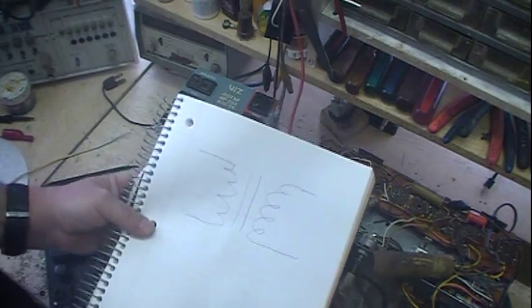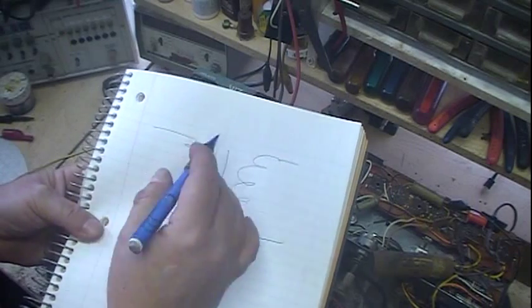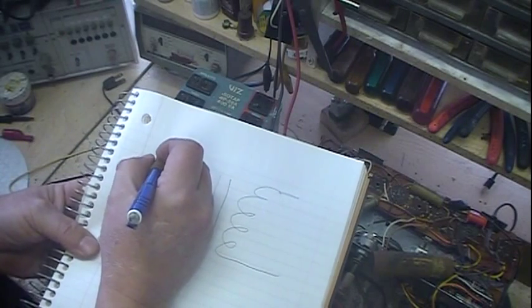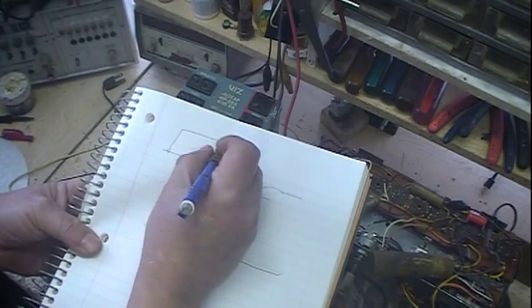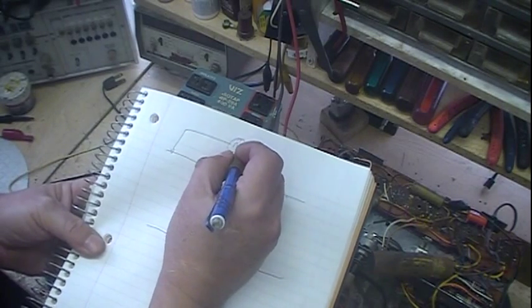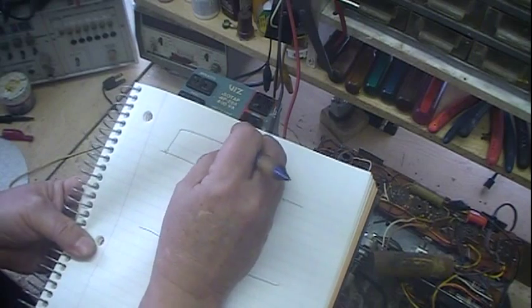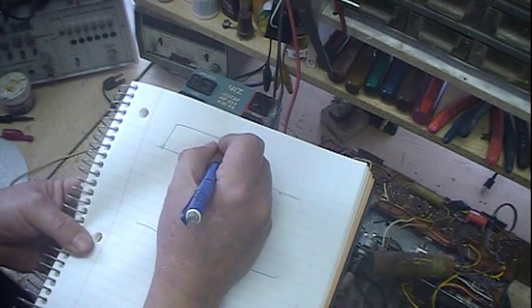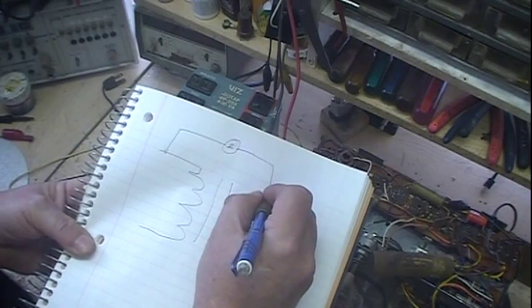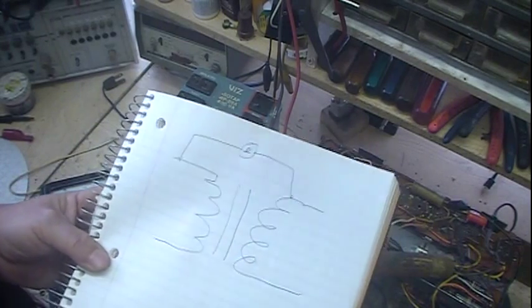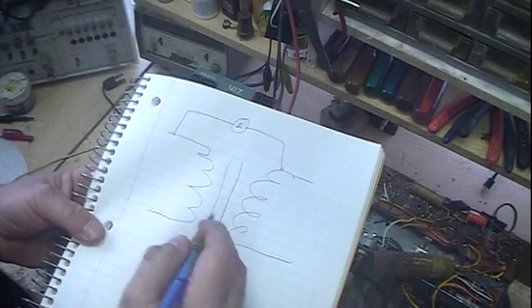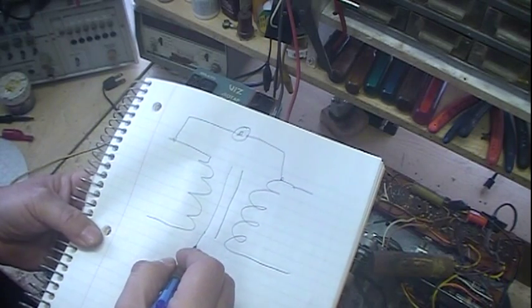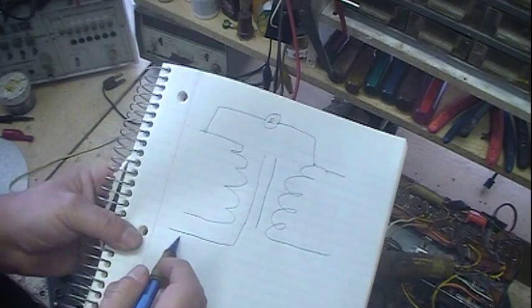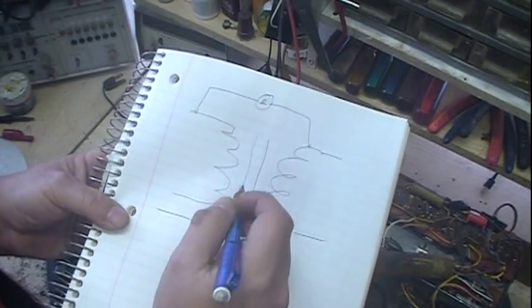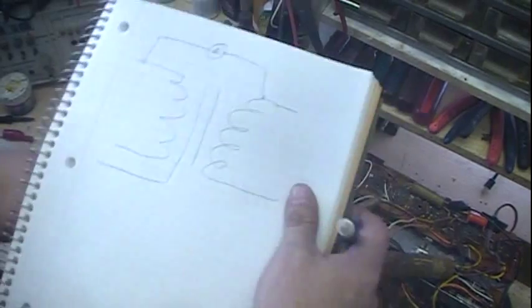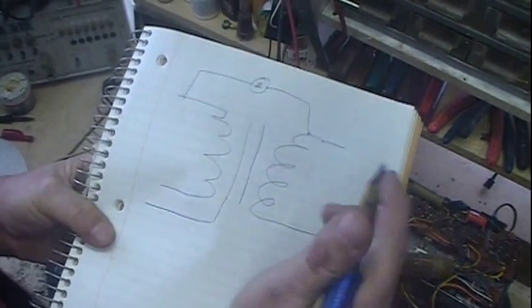What I was doing with the meter is connecting, say right here, going up to my ohmmeter, set to ohmage, not AC, and going down here. On the isolation transformer we've got a 3-wire plug, and that third wire is going right here - it's the ground that hooks to the core and some of the metal casing.